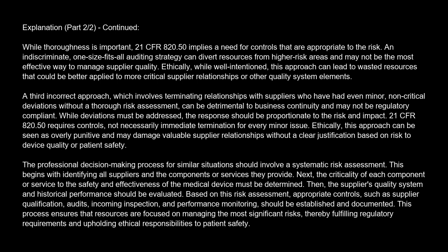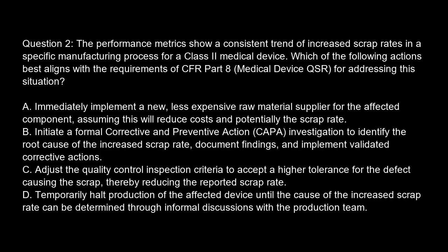Based on this risk assessment, appropriate controls such as supplier qualification, audits, incoming inspection, and performance monitoring should be established and documented. This process ensures that resources are focused on managing the most significant risks, thereby fulfilling regulatory requirements and upholding ethical responsibilities to patient safety. Question 2.